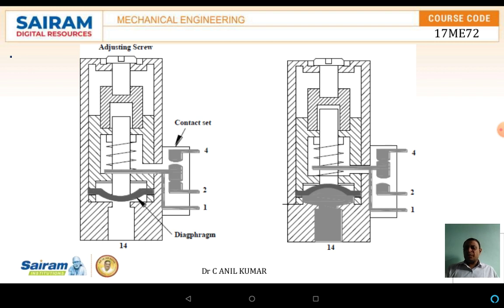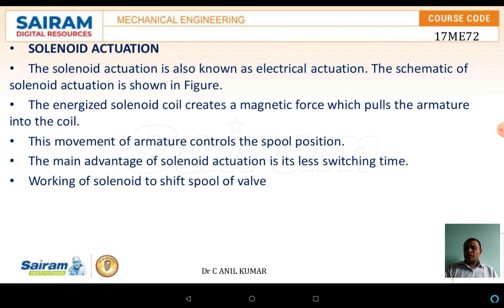In this pressure switch, the lower portion is something like a concave form. A bellows or a diaphragm is there. When some pressure is applied from the bottom, it expands or stretches. Once it stretches, the make or break mechanism automatically takes place. Automatically the motor switches on or off, depending upon the type of application in the circuit.